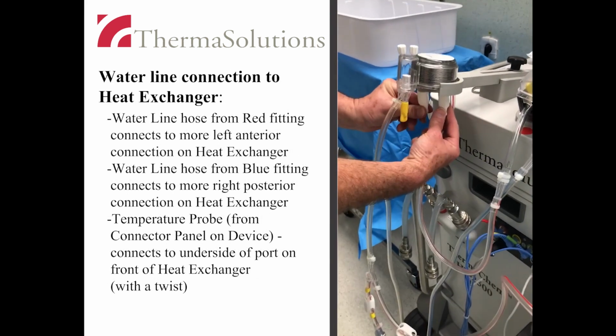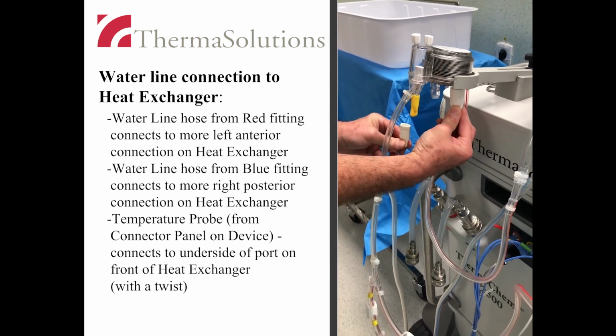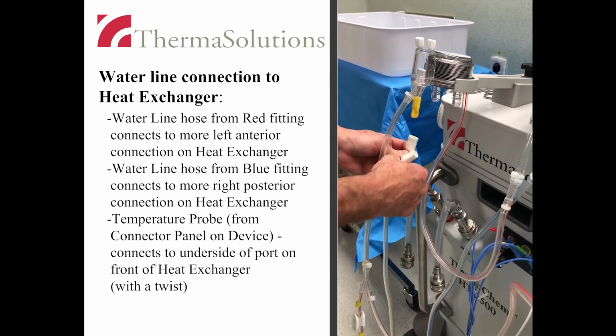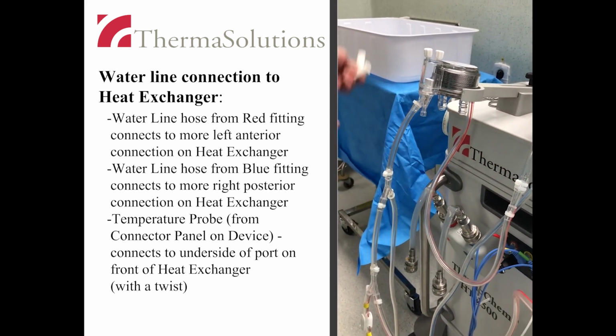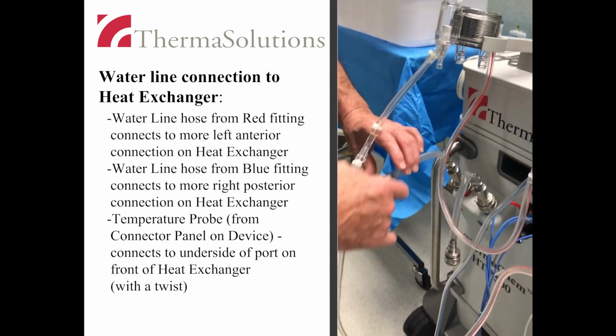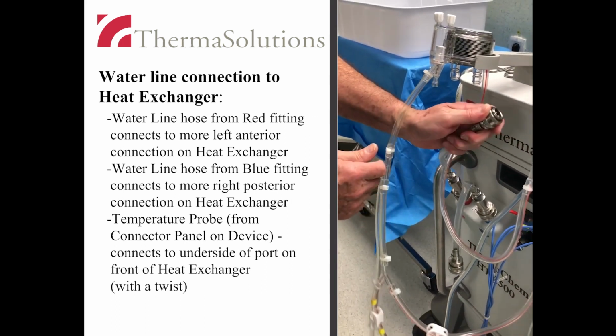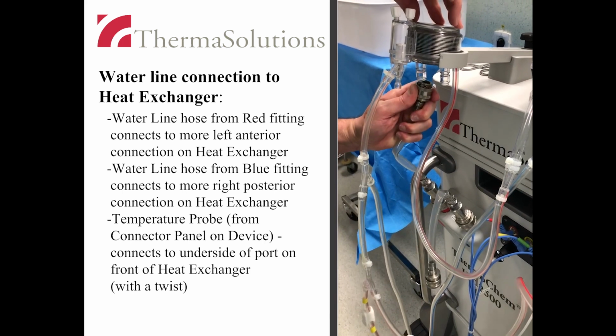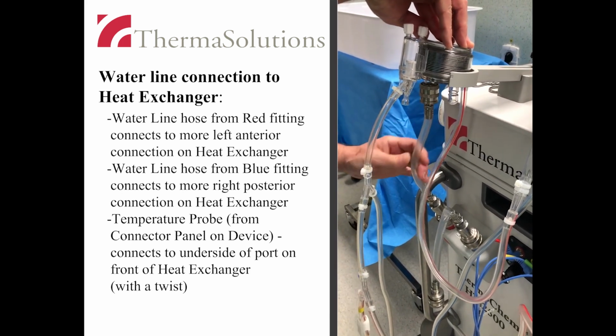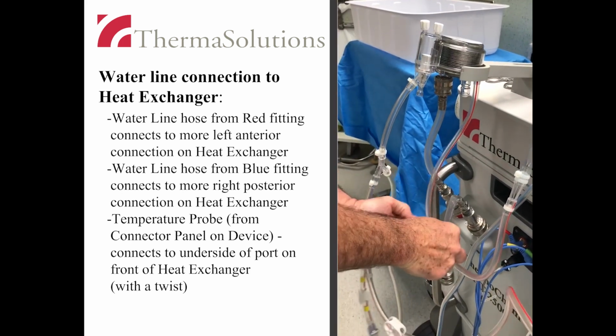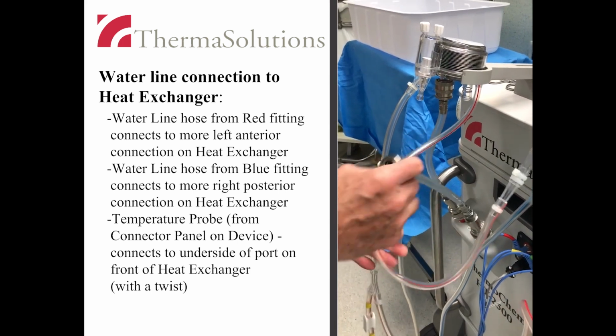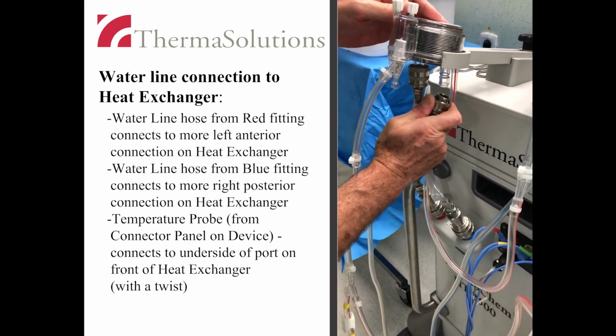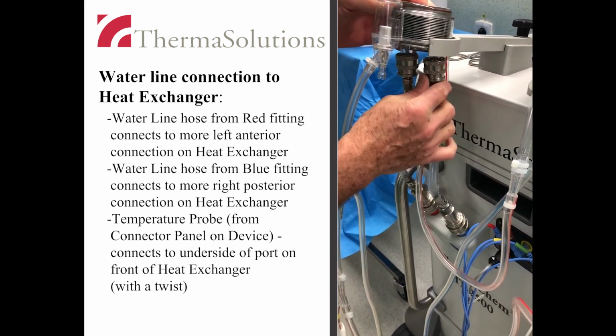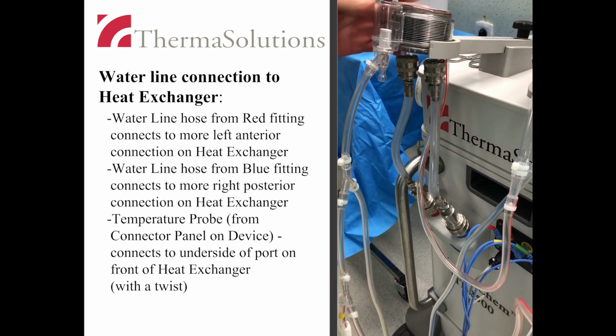Next, connect the heat exchanger to the water bath system using the following steps. Attach the water lines to the heat exchanger by pulling the spring collar down and snapping it into place on the underside of the heat exchanger. An audible click should be heard. Test the connection to see if it is secure. When attached correctly, the water lines will be parallel to each other and not crossed.